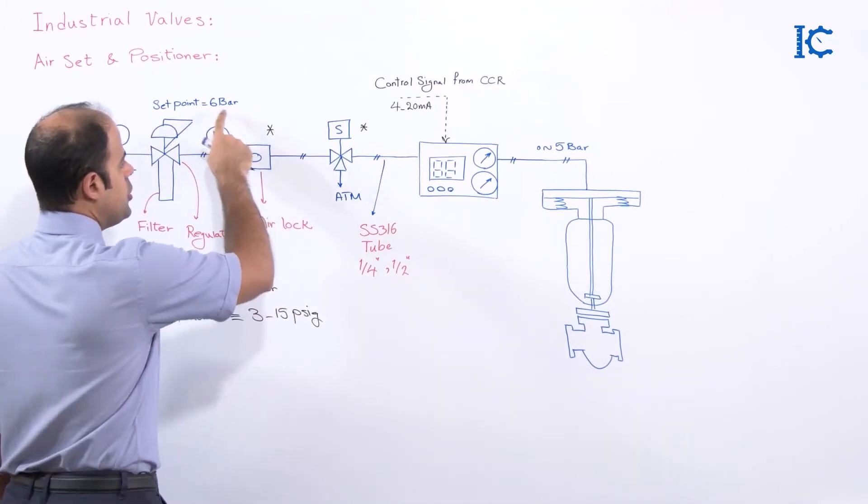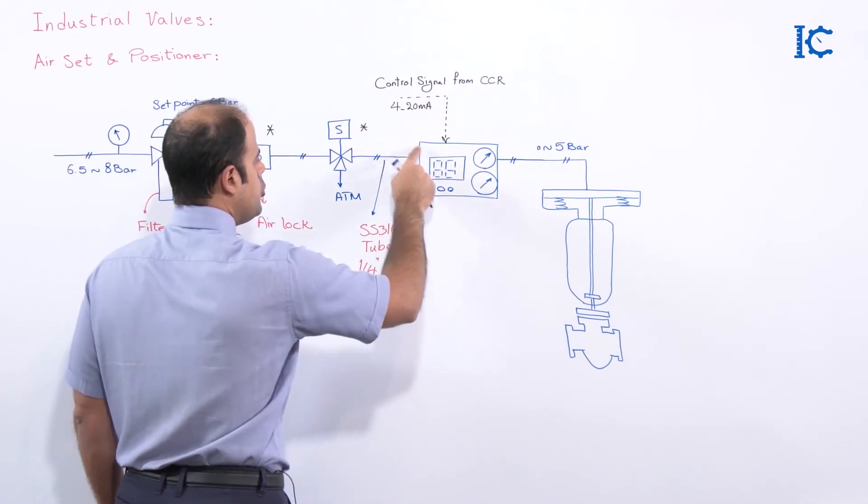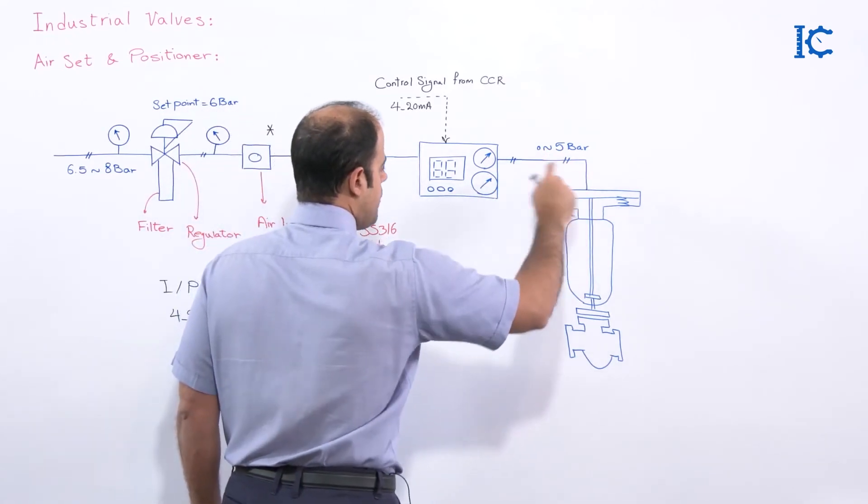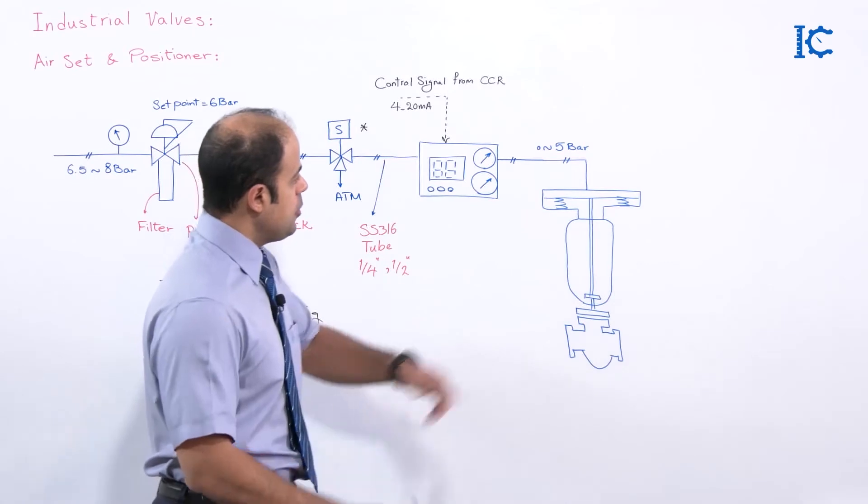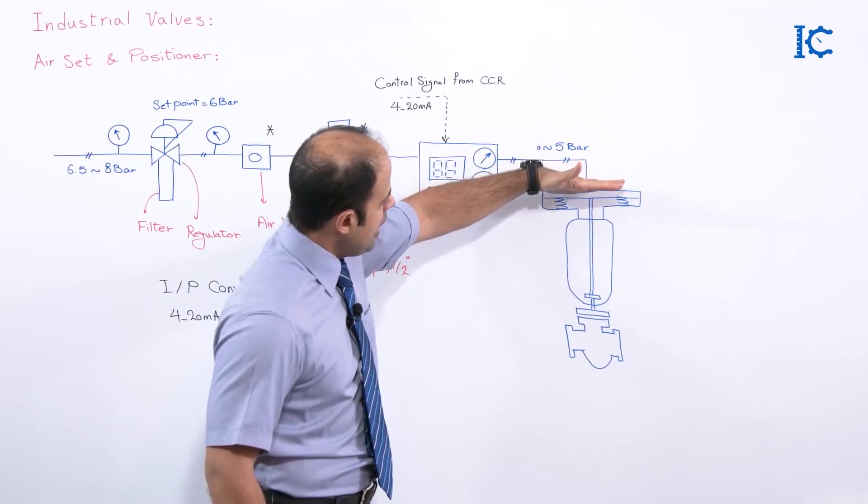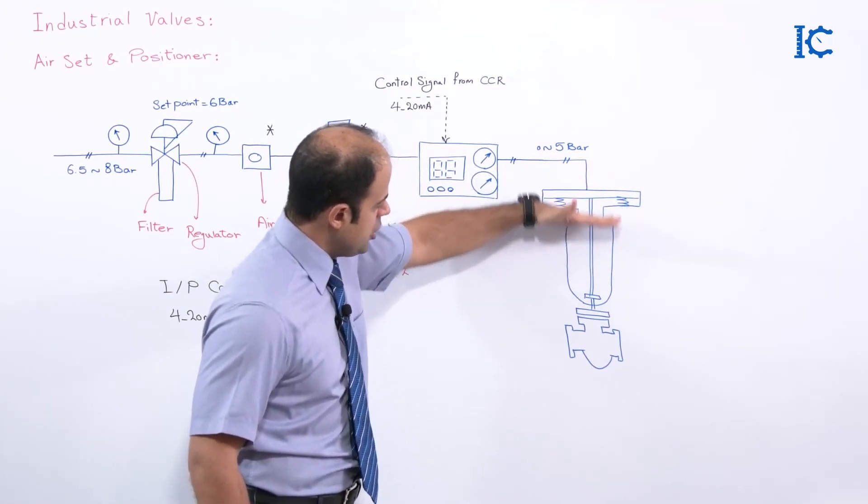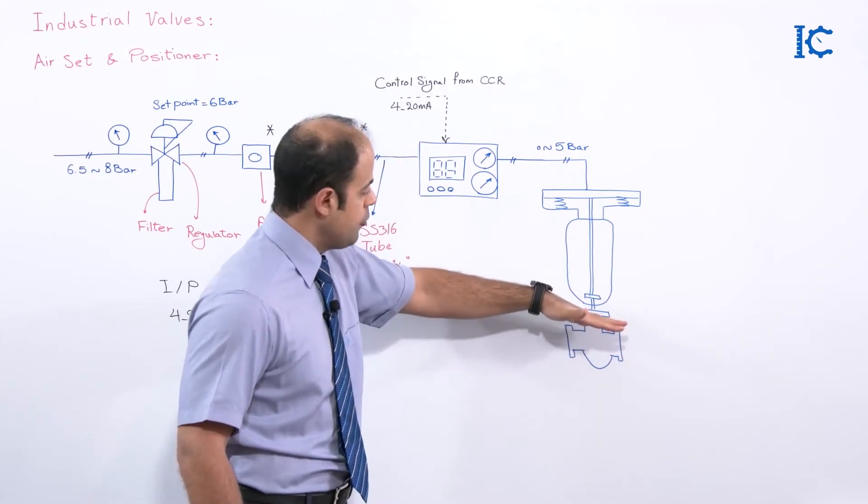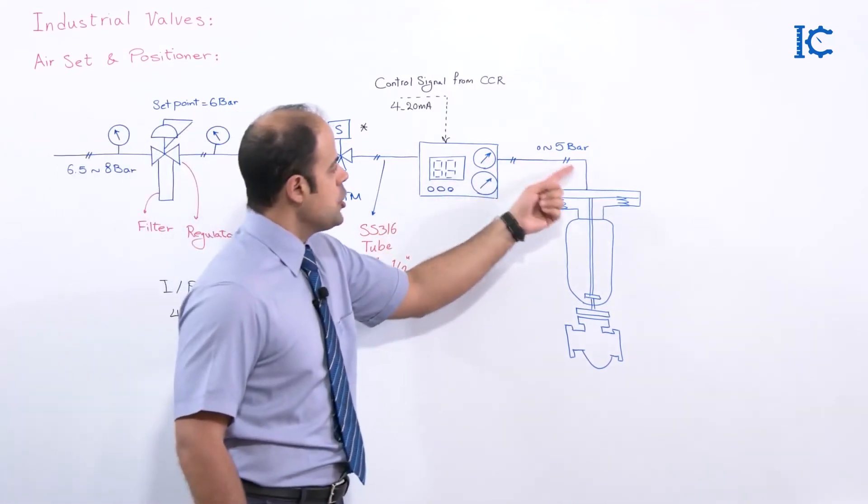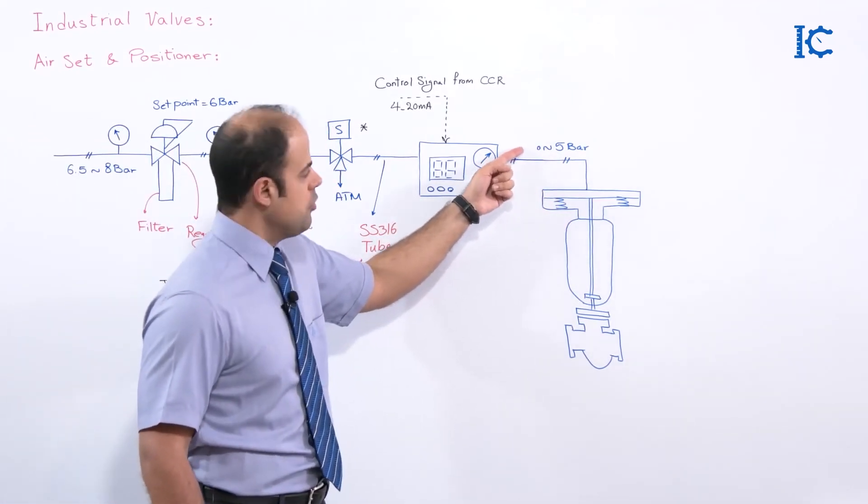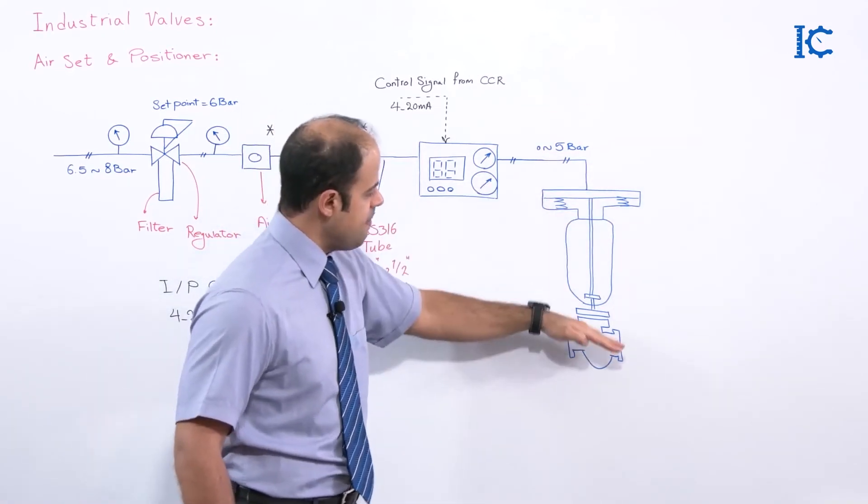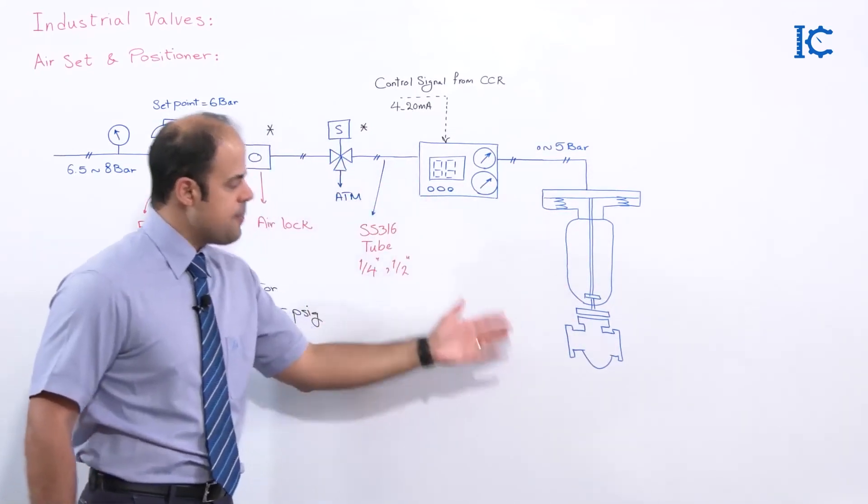So do not forget the pressure that we have inside of the positioner would be around 6 bar. I said that approximately at maximum case we have 5 bar here. So as you can see, the time that the pressure of this line is around 5 bar, it means that the valve is going to shift down and then close the valve. And for sure the pressure of this line is going to be close to 0. There is no pressure, and in this case the force of the spring causes that the valve would be opened up.